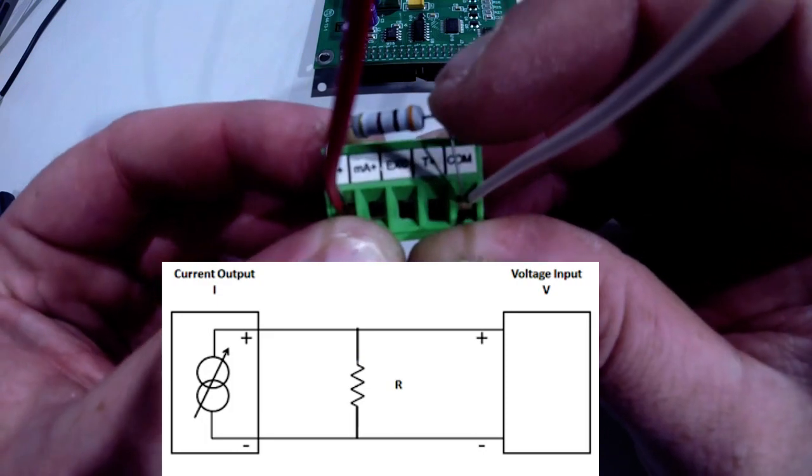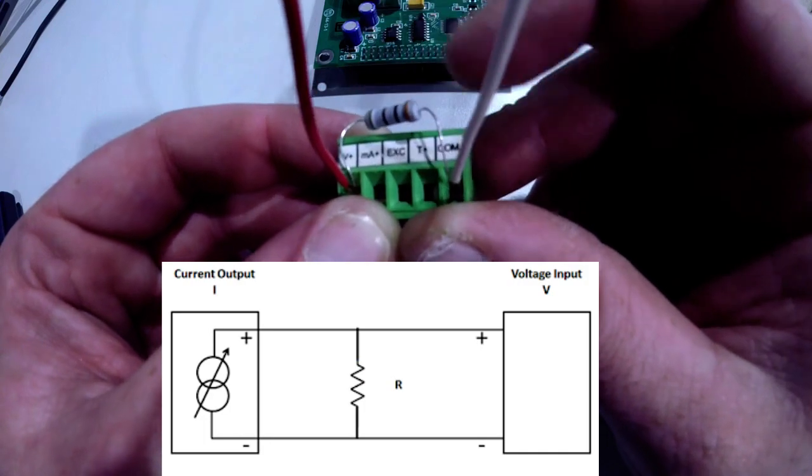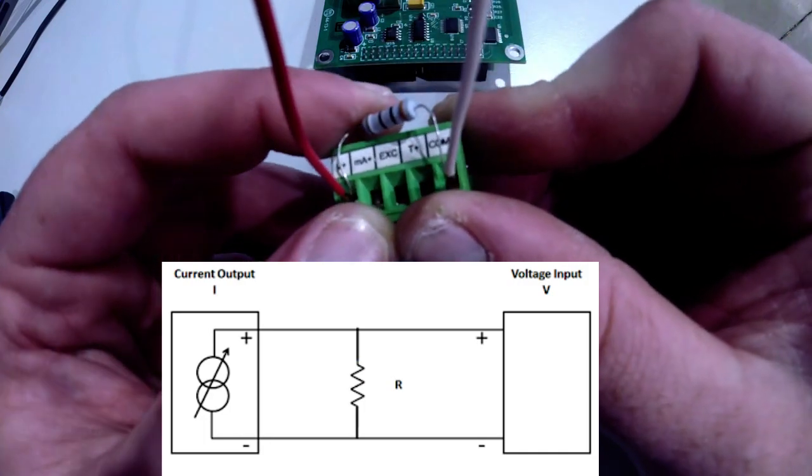I don't know if you've noticed the color code on this resistor, but this is actually a 250 ohm resistor. If we put two of these in series, we can actually make our 500 ohm resistor. So right now in this configuration, if we were outputting 0 to 20 milliamps, at zero we would have zero volts.